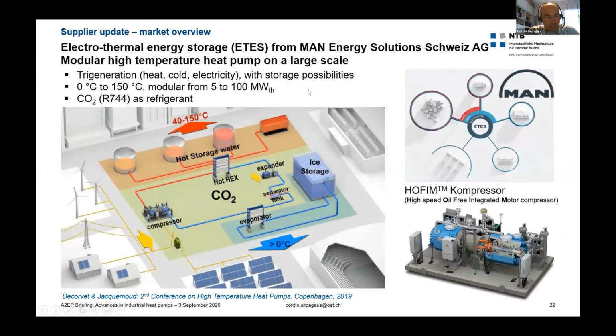Then I'd like to show this slide. It's from MAN Energy Solutions in Switzerland. It's an electrothermal energy storage system, also a very large system. The smallest is 5 megawatts thermal energy. The core of this system is the Hofim compressor, coming from the gas industry, using CO2 in a heat pump cycle. It produces heat, it can produce cold, and it also can produce electricity when reversing the cycle, so it's called a tri-generation system. Very interesting if you are at very large scale.